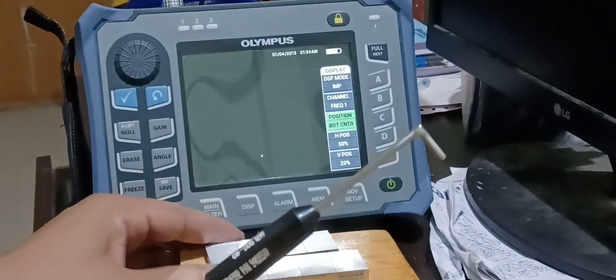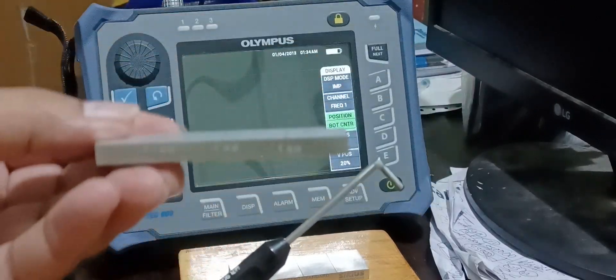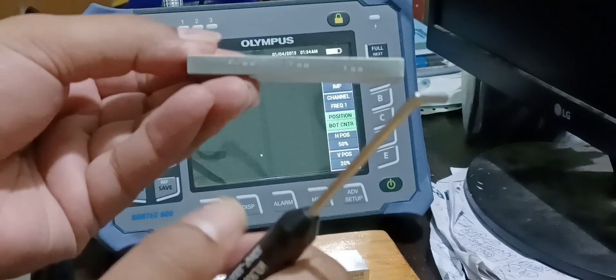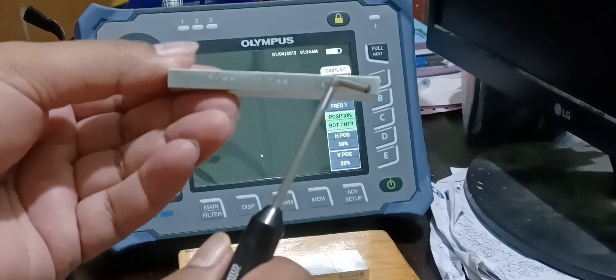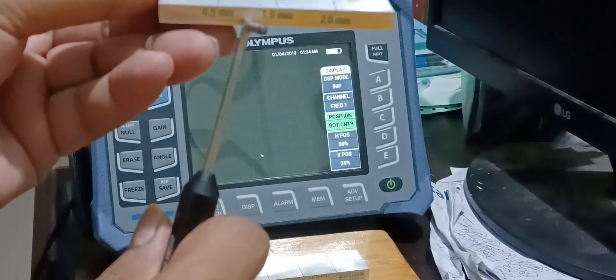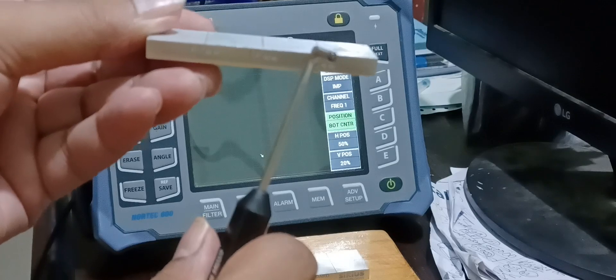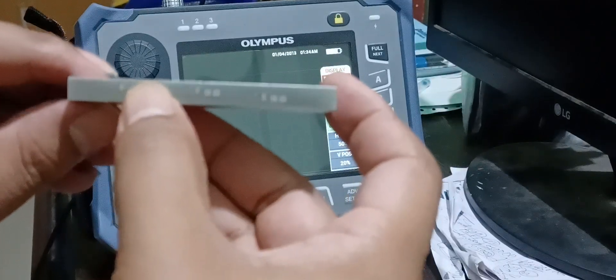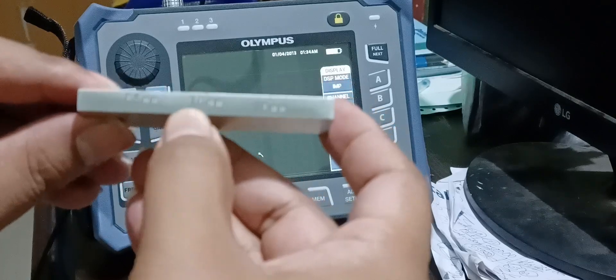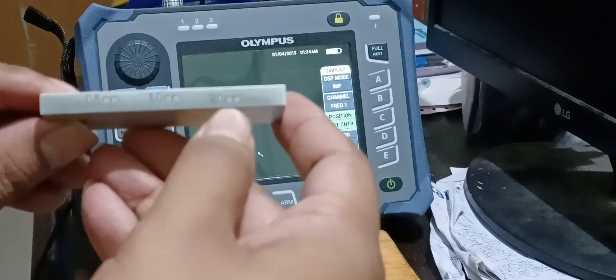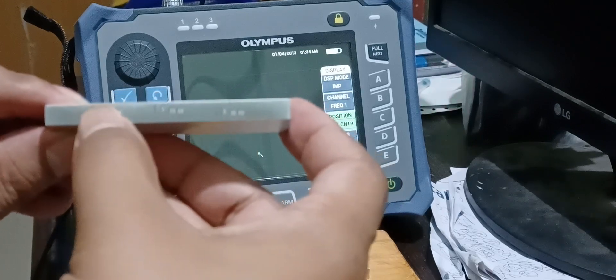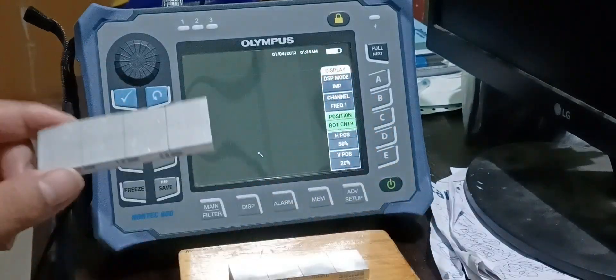Now, I will show you, this is an aluminum crack specimen. This is having three depths. One is 0.5 mm. One is 1 mm. And one is 2 mm. This is a surface notches. You can see the surface notches. This is 0.5 mm. This is 1 mm. And this is 2 mm depth from the surface. You can clearly see. This is 0.5, 1 mm, and 2.0 mm depth from the surface. This thing is made of aluminum.